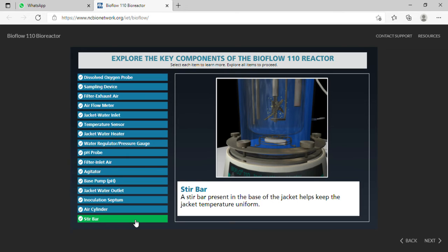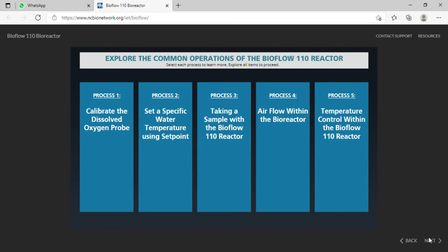Stir bar. A stir bar present in the base of the jacket helps keep the jacket temperature uniform. Next, the common operations of the Bioflow 110 reactor. The first process is to calibrate the dissolved oxygen probe.